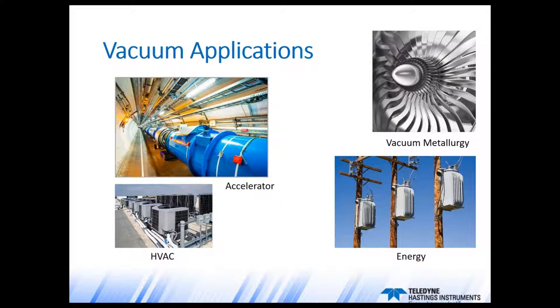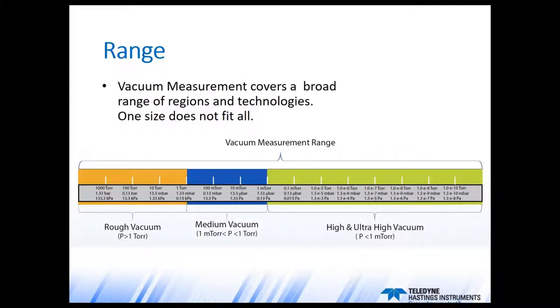Now let's get on to number one on our list — range. All of these different applications cover a very broad range of pressures. Surface analysis systems and particle accelerators can reach below 1×10⁻¹⁰ Torr, and there are some vacuum drying applications that may only require 100 Torr. Vacuum measurement covers a broad range of regions and technologies, and there's not one single technique that's going to cover them all. There are combination gauges that combine techniques to cover a broader range.